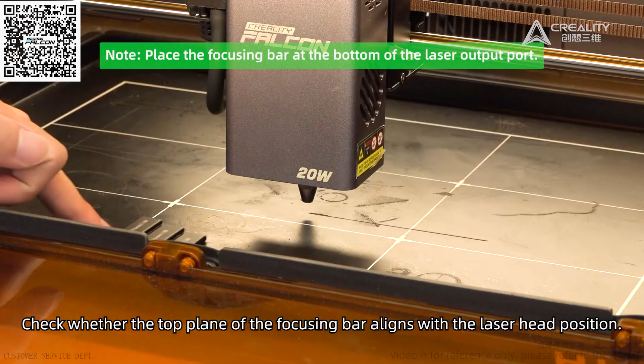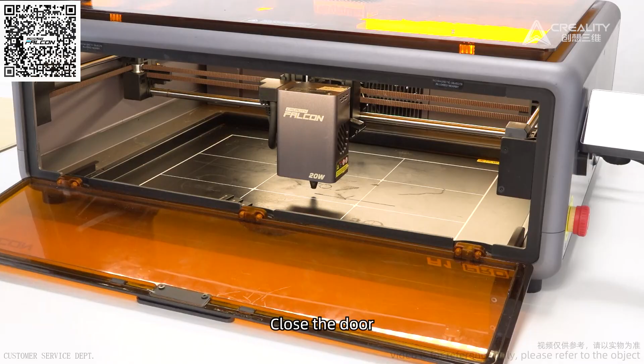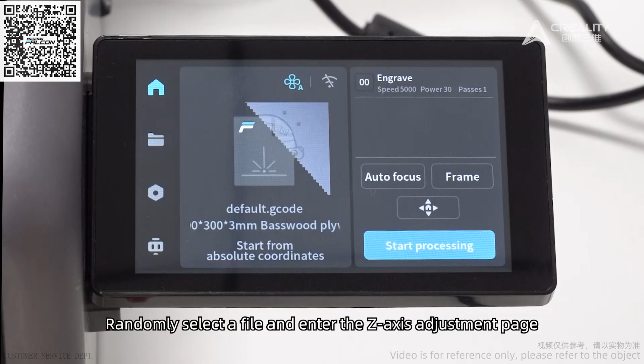Power on. Check whether the top plane of the focusing bar aligns with the laser head position. If not aligned, adjust the position by lowering or raising the Z-axis to achieve a proper fit. Close the door. Randomly select a file and enter the Z-axis adjustment page.